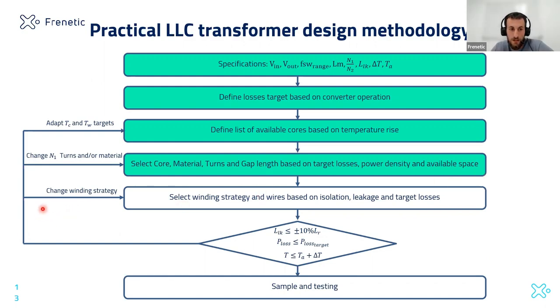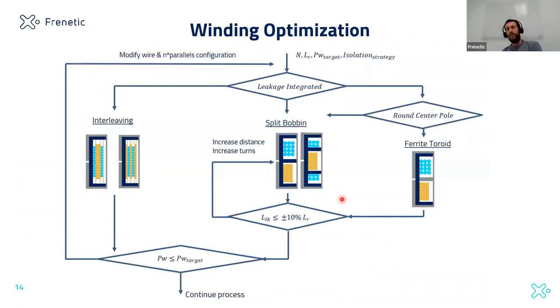Now it's time to select the wire of our magnetic, the positioning of the windings. So how to do that? What we need to ask ourselves first is whether we want to have the leakage inductance integrated or not. That is, whether we want to have the series inductor integrated as the leakage inductance of the transformer or not. If we don't want to have it, this means that we have two components, one separate inductor in series with the transformer, then what we are looking for is an interleaving winding arrangement like the ones I have here. So this is partial interleaving.